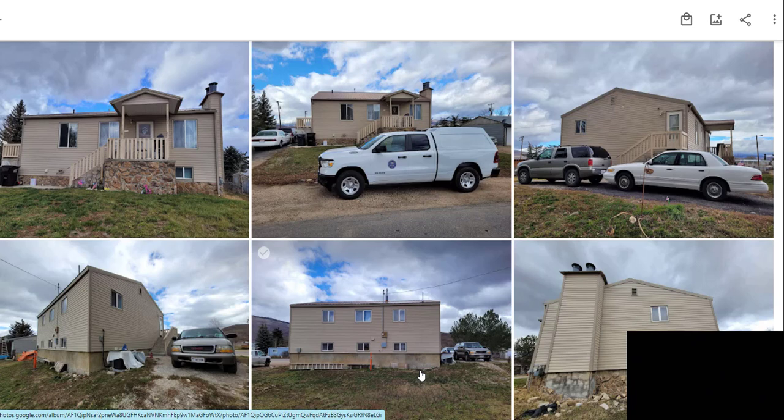So the whole point of the dwelling height on ASHRAE is to allow for stack effect. And I know a lot of times you'll look at these and you'll go, well, that foundation's pretty airtight. Shouldn't we just measure from right here up? No, the standard is that we measure the lowest above grade point to the highest above grade point in the pressure boundary. If this had a vaulted roof or a vaulted ceiling in it, then we would be measuring from the lowest point that we've found out here, and then we'd measure up to wherever the highest point on that vaulted ceiling was.